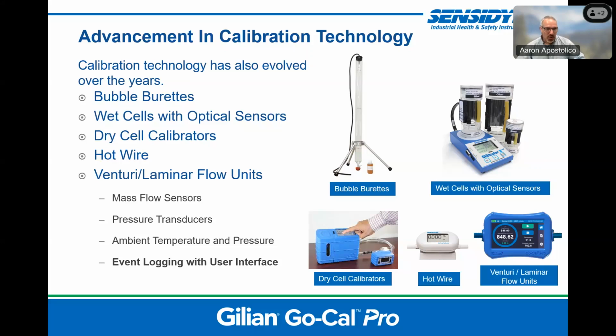And then we come to our newest products and newer technologies, which include the Venturi laminar flow units. Now, while Venturi laminar flows have been around for a long time, the sensor technology has improved, allowing us to achieve that 1% accuracy across the flow range. These mass flow sensors and pressure transducers, as well as your ambient temperature and pressure sensors, give added metadata to record and actually use for comparison of your event.